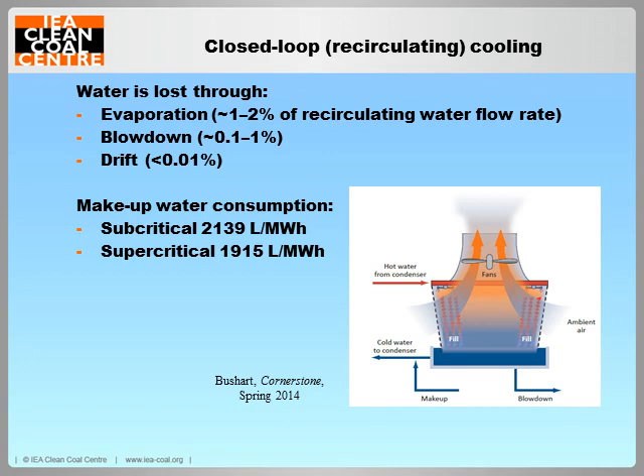As you can see from figures on this slide, evaporation accounts for the highest loss, around 1 to 2% of the recirculating water flow rate. I've also included some figures for make-up water consumption to give you some idea of the amounts involved. I'm just going to look at reducing evaporative water losses. The full report does include blowdown and drift.